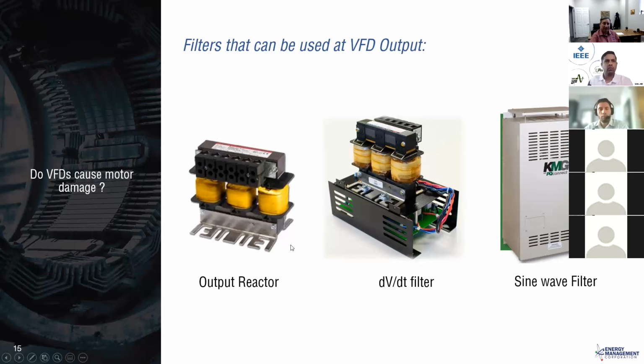so they're usually rated with being able to handle a certain frequency spectrum. The one that we're using nowadays is imported from Germany, and it's a polygap. So they've distributed the air gap on the core of this reactor, and we found it to be a phenomenal performing reactor. And so we would use that kind of a reactor probably easily up past 500 feet of cable length. When we start approaching 1,000 feet, we're going to turn to a DVDT filter.